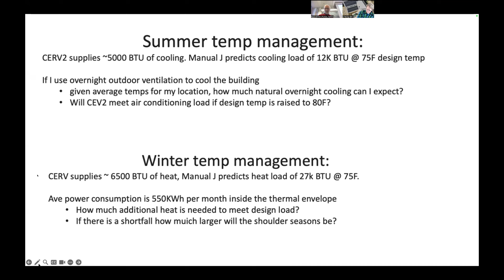Do I actually need a mini split to stay warm over the winter? If I can't manage to do it in the coldest period, how much wider is my shoulder season where I don't need supplemental heating or cooling? By one metric, you should design heat pumps to only provide heat up to 80-85% of your design load, because otherwise your equipment is oversized. When you hit that design load limit, you supplement with electrical resistance or backup forced air. So how much bigger are my shoulder seasons? I don't know. Here's another problem.